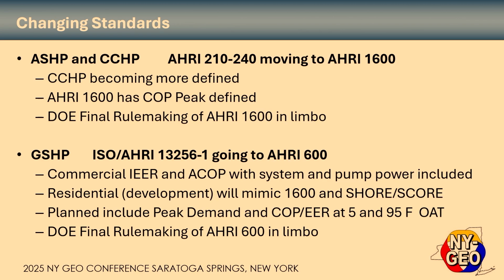1600. And 210, 240, if you're not familiar, that's the SEER 2 and HSPF 2. That's where that comes out of. And it's going to be moving to a new standard, and they're trying to get that through the DOE right now. And of course, with all the changes in Washington, that's a little up in the air as to whether or not 1600 will actually be adopted here. But the cold climate heat pump is a lot more defined in 1600, so there's some good things out of that that'll help regulate the market with that.